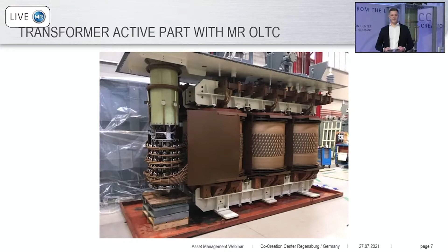On this overview photo, you see that the tap changer is installed in the transformer main tank and connected to the regulating winding. The tap changer itself is divided into the main components, which you can see here on this overview. We have the OLTC oil compartment. Inside, we have the diverter switch insert, and below, we have the tap selector. On the left, you see the movable contact system. This is the inside view of the DSI. And below, the transition resistors, which you can also find on the diverter switch insert.